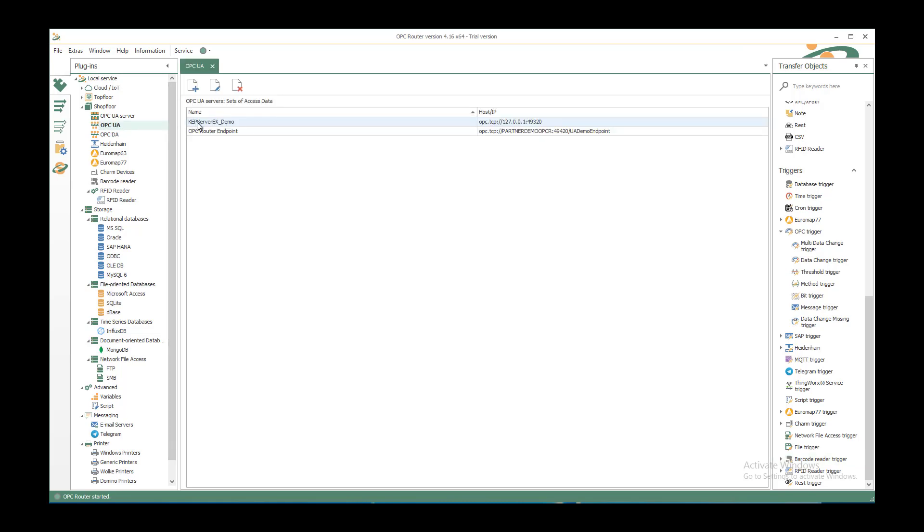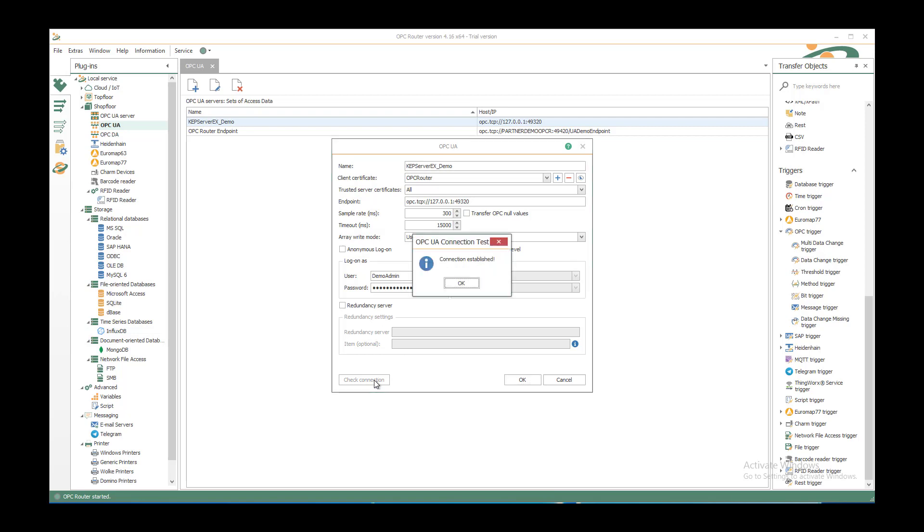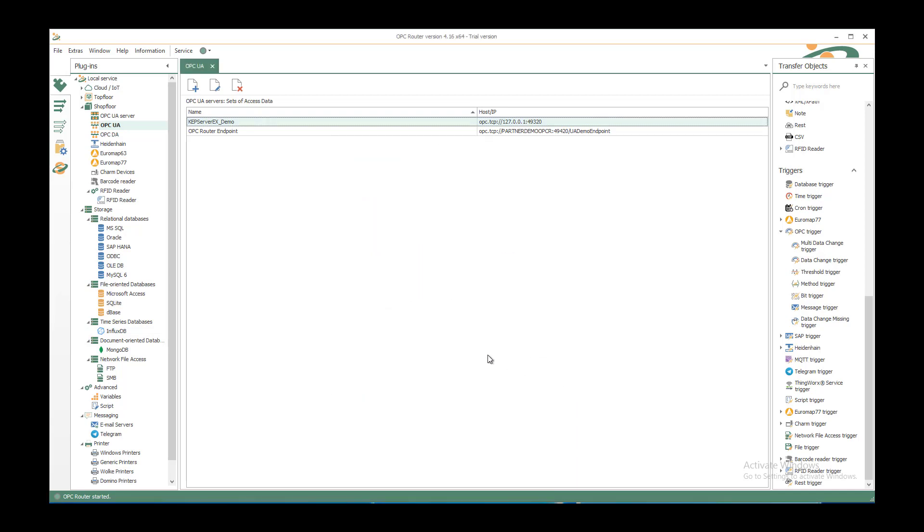You can select the predefined OPC UA server or create a new one. I show you my configuration. I have created a client certificate with the plus button and selected an endpoint, logged on as a specific user with the highest security level available at the target OPC UA server. I can check the connection to make sure it's established. It's OK. If you want to save the changes you can use the OK button.